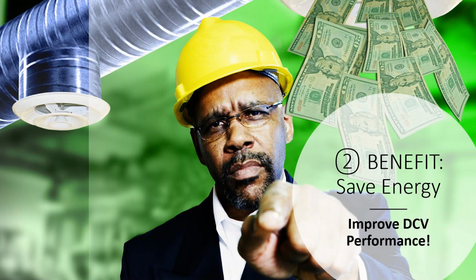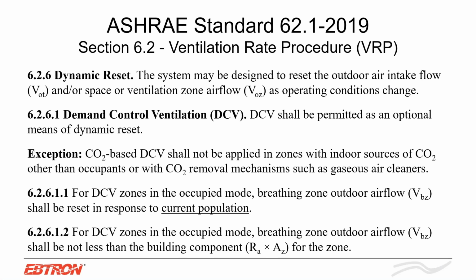So let's talk a little bit about DCV. What is DCV? Demand control ventilation basically is bringing in the required amount of outside air to the space based on the space type and based on the population, right? So you are staging your system to bring in outside air depending on the population of the space. Traditional methods for this are a CO2-based DCV strategy, where typically you're maintaining around 1,000 or 1,100 parts per million in the space. But let's look at how we can improve that, because there are some issues with that, right? What does ASHRAE say?